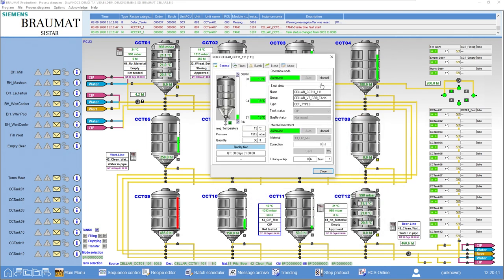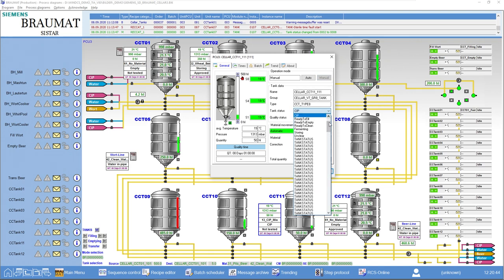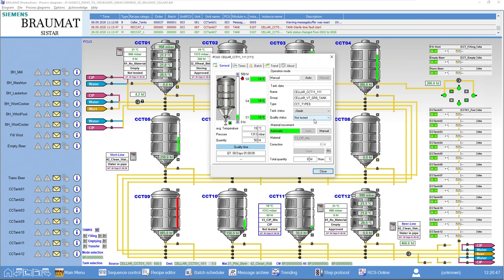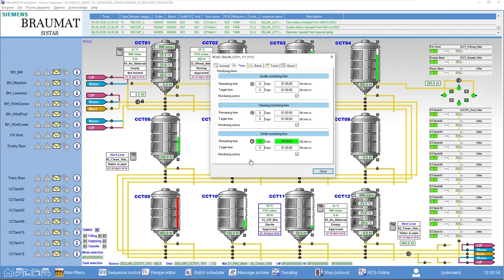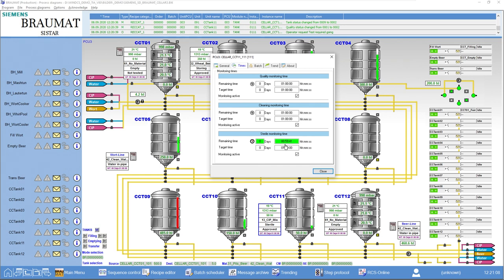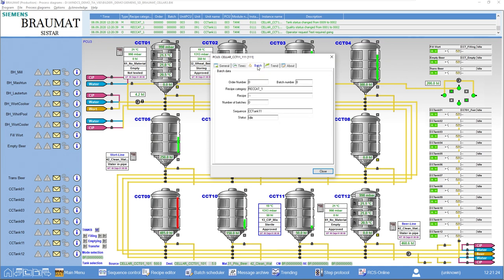For example, we have sterilized or cleaned the tank, which I'll do manually here. And the operator has acknowledged it. A sterilizer timer with a predefined time will start. After this time, the tank should have been used, in other words, filled. If this does not happen, you will receive corresponding messages. Please re-sterilize the tank after this time. The same applies when cleaning or if you have carried out testing in general. So that's the intelligence within the module.